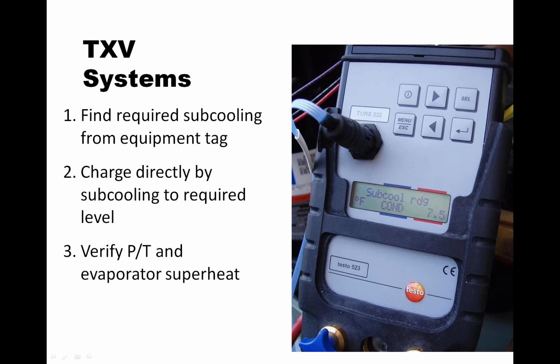To make sure that if we have the correct amount of subcooling, we also don't have excessive amounts of total superheat. In other words, we said 8 to 12 degrees of evaporator superheat, and if we have a port at the evaporator outlet where we can measure, that's where we're going to measure it. But if we don't have that point, we're going to have to look at total superheat, and typically that total superheat should be between 12 and 20 degrees. If we get over 20 degrees of total superheat, you better add insulation to that line set, because you may not provide adequate cooling for the compressor, and you may have a failure there.